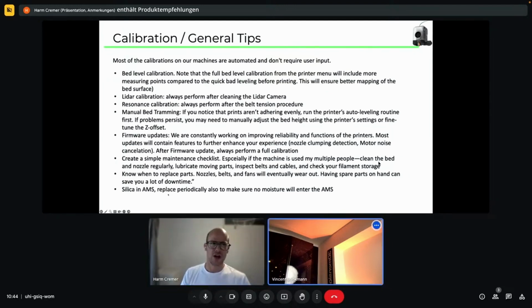Another quite important part is the silica gel in the AMS. The AMS comes with silica gel in it, and this needs to be replaced after a while. It's hard for us to tell you exactly when, though we do have the indication in the software from 1 to 5 water drops, where 5 is a really high moisture level. But we still can't tell you exactly when this will happen, because it depends on external influences, like how much moisture is in the air in the room you're using it in. Still, it is very important to keep track of this.